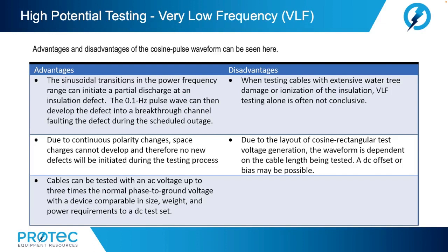Now, let's take a look at some of the advantages and disadvantages of the cosine pulse waveform. Among the advantages, the sinusoidal transitions are in the power frequency range and can initiate a partial discharge at an insulation defect. The 0.1 hertz pulse wave can then develop the defect into a breakthrough channel, faulting the defect during the scheduled outage. Also an advantage, due to continuous polarity changes, space charges cannot develop and therefore no new defects will be initiated during the test process. Another advantage, the cables can be tested with an AC voltage up to 3 times the normal phase to ground voltage with a device comparable in size, weight, and power requirements to a typical DC high pot test set.